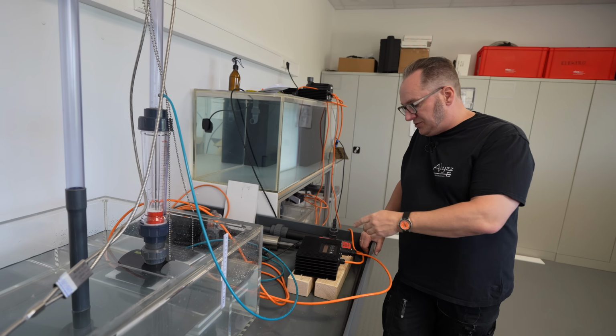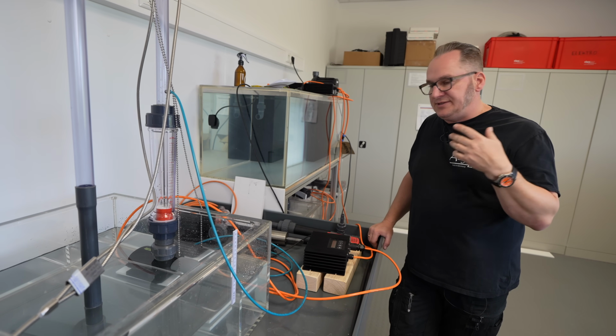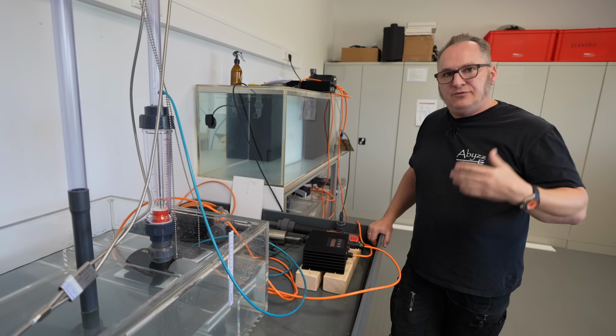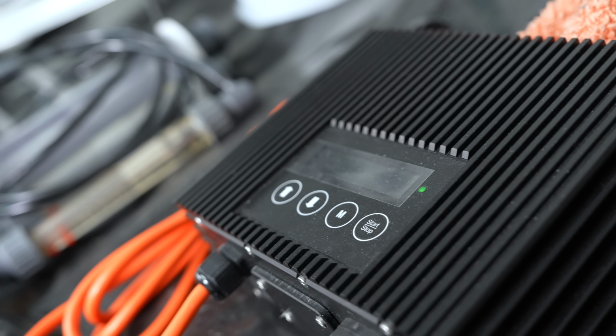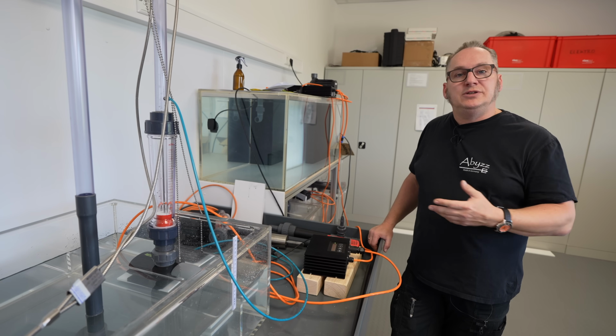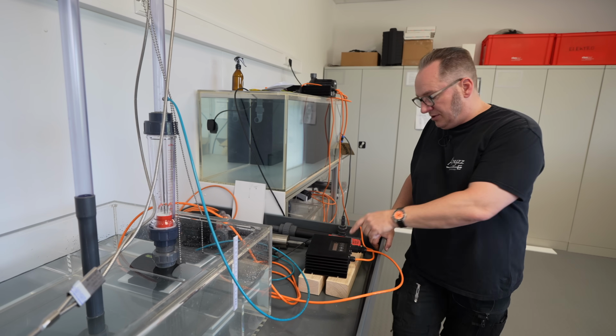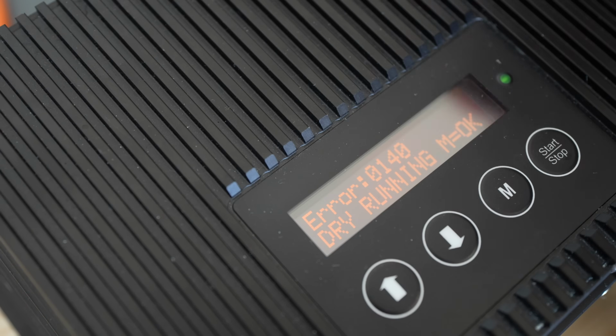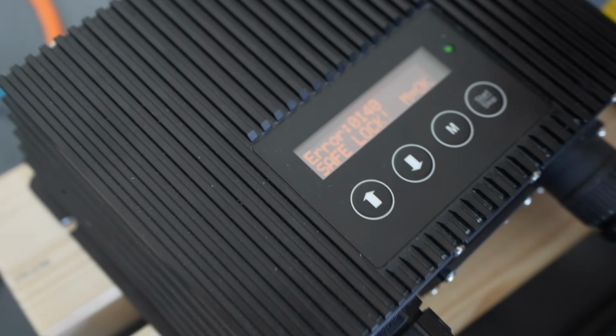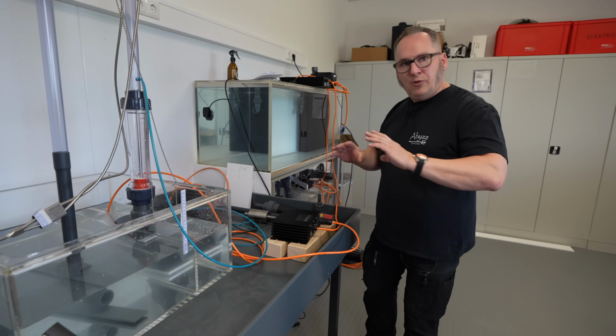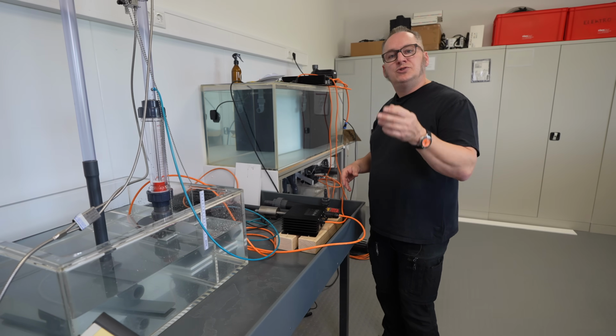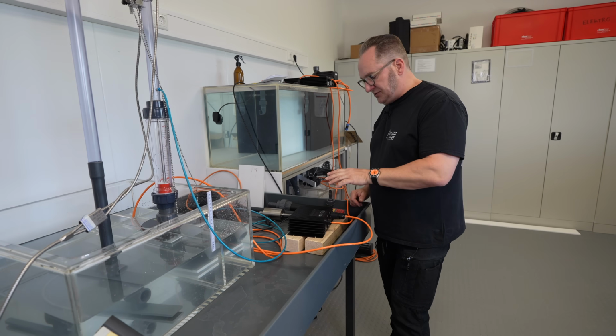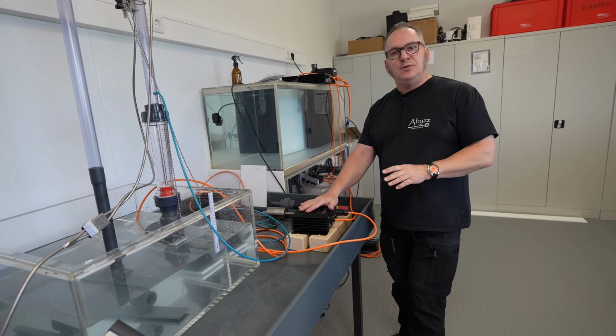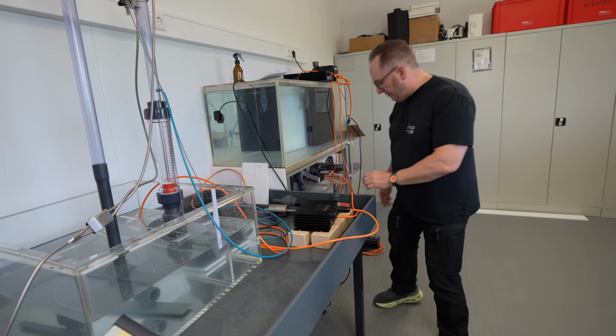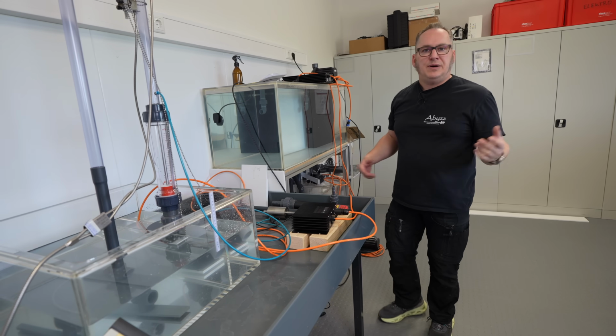What will happen is that the driver at some point will go into safe lock. So if the same error continues to happen for a couple of times, then the driver will lock itself out to make sure that the pump doesn't start up like 1,000 times and then actually gets damaged. At some point it will go to safe lock, and you see that right here. If it's safe lock, which is the error 140, before you confirm the errors, they are always written in plain text. So just make sure to read before you press any buttons. So safe lock means you cannot switch the pump on anymore on the driver. What you have to do is repower the driver, and then the pump will start up normally.